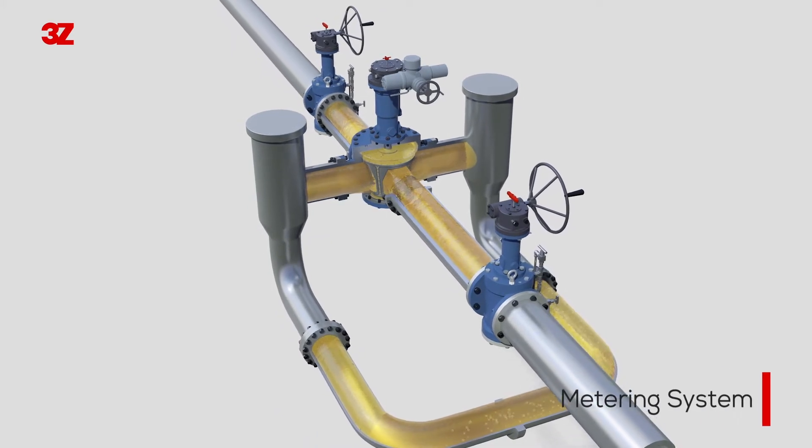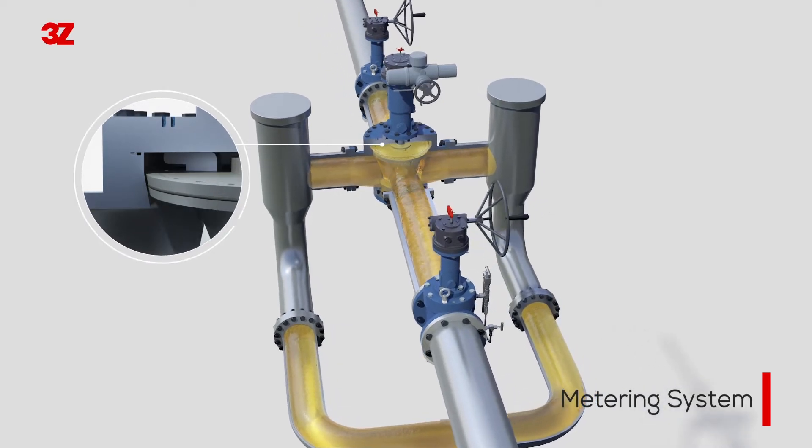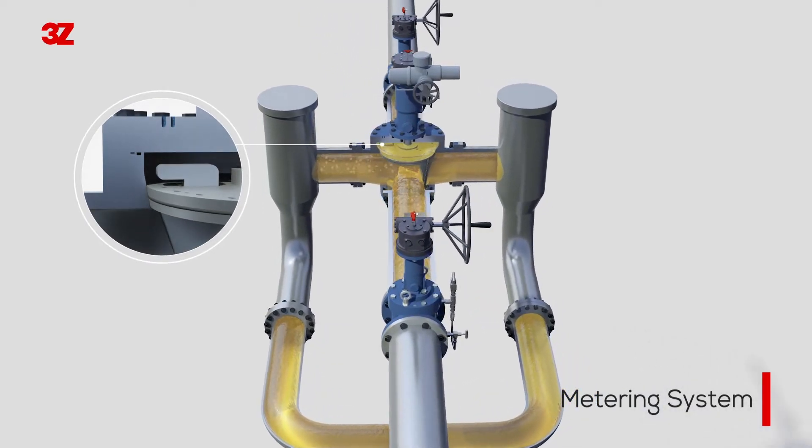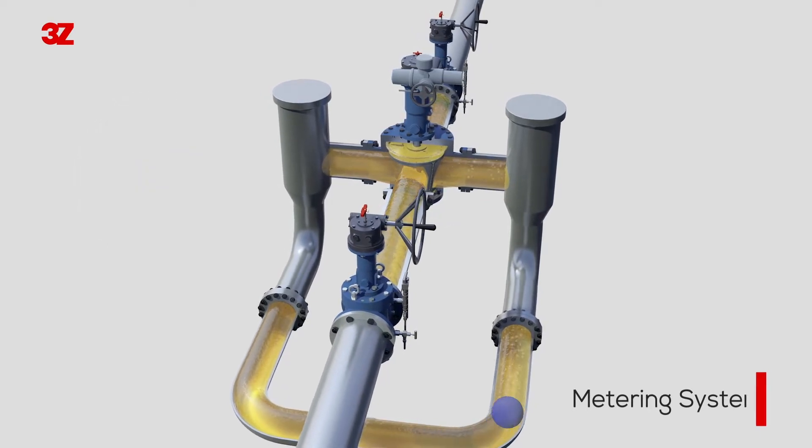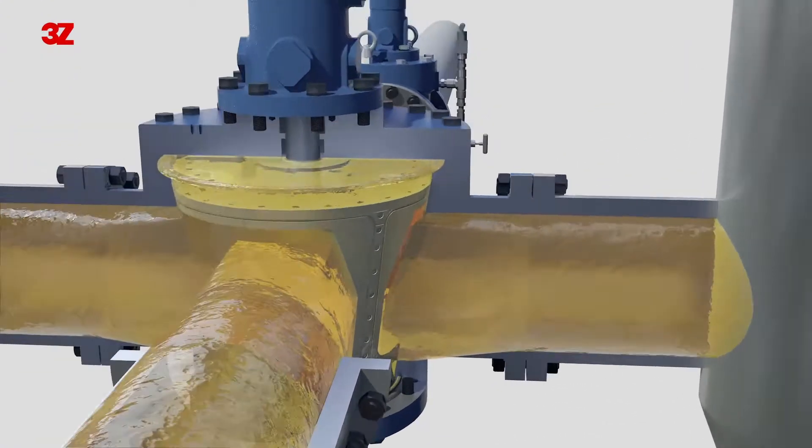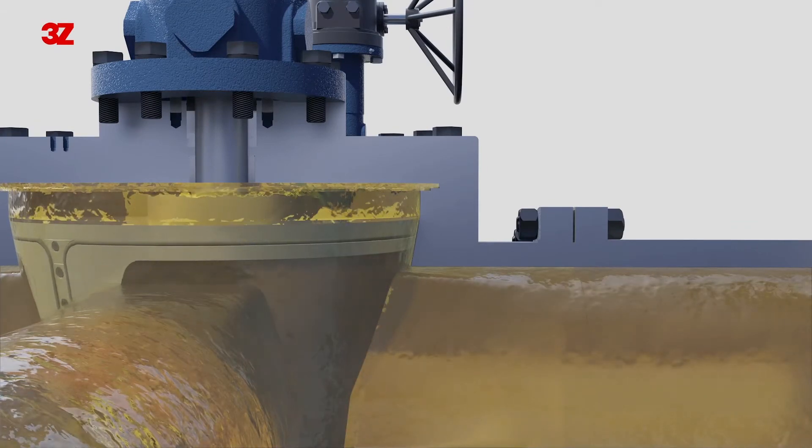The soft seal is in contact with the body while the valve is in normal position, but there is no friction during operation because the soft seal and body are not in contact with each other. As the soft seal and the body are in contact with each other again only after the operation is completed, this minimizes the abrasion of the soft seal.